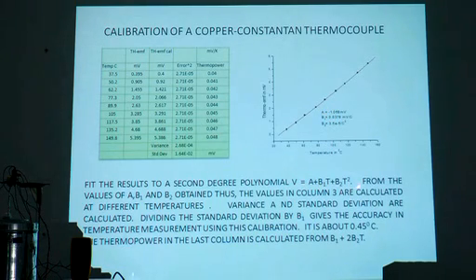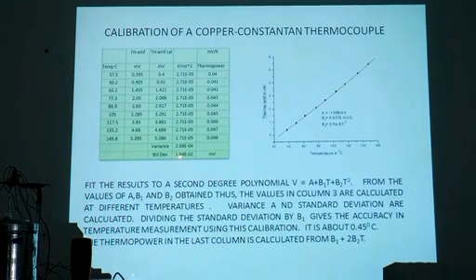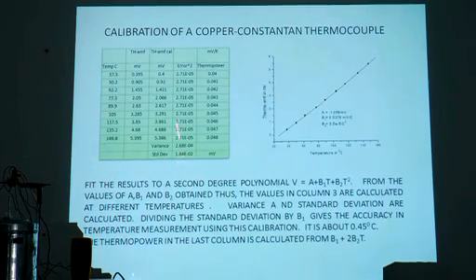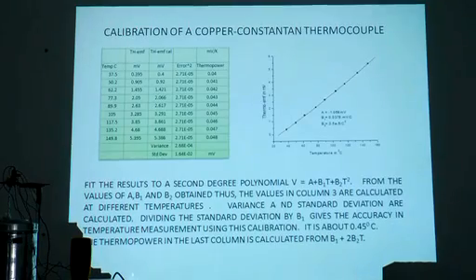If you differentiate this equation with respect to temperature, that gives you B1 plus 2B2T. At any temperature, the value of B1 plus 2B2T is the change in the thermo EMF for 1 degree change in temperature. That will be about 40 microvolt per degree. The error here is 1.64 times 10 power minus 2 millivolt. So, you multiply it by 1000, it will be 16.4 microvolts. 40 microvolts is 1 degree, 16.4 microvolts will be 0.4 degrees. So, if you use this thermocouple to measure temperature, you will get the temperature to within plus minus 0.4 degrees centigrade.